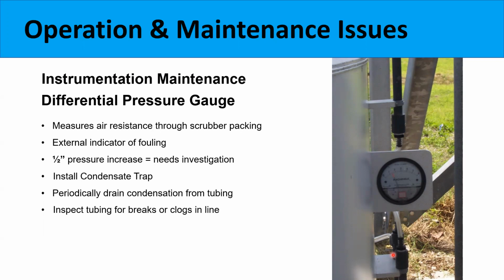A lot of times trending that differential pressure information will allow you to make a determination if you need to go investigate a pressure drop situation. We recommend monitoring not only the differential pressure on the pack section, but also that composite mesh pad outlet section of a scrubber, which is more prone to plugging than the pack section.